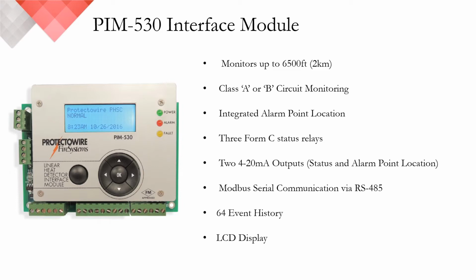Other features include Class A or Class B monitoring, integrated alarm point location, communication to the main panel through Form C status relays or 4 to 20 milliamp outputs. We've also included a 64 event history file as well as Modbus serial communication.